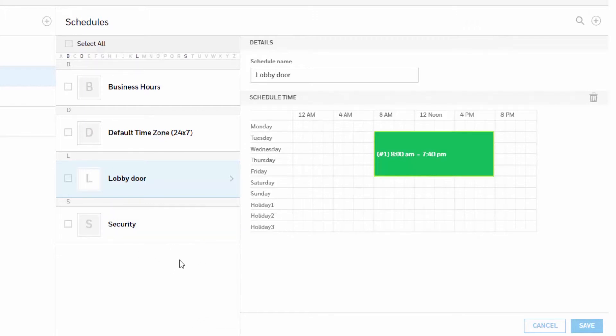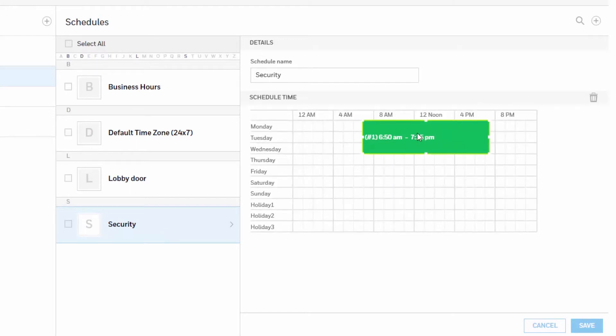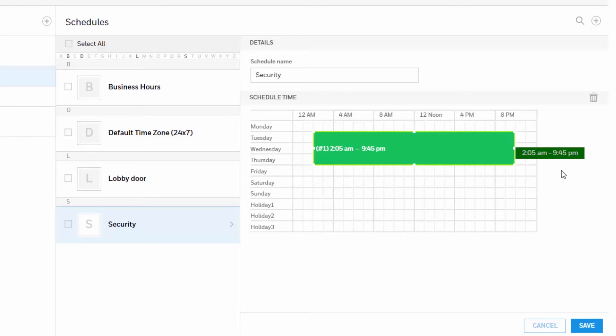To modify a schedule, locate the schedule in the alphabetical list located on the left side of the window and select the name. Click to select the desired schedule, then click to select the rectangle that defines the schedule. Drag to change the shape and therefore the days and the time of the schedule. Once you are done, click save to accept all the changes.